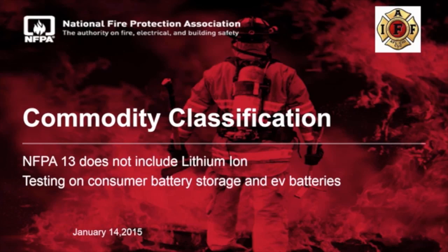But when we put the batteries into an electric vehicle, looking at somewhere around a 300-volt battery, our actual field fire tests showed that if water is used as a suppression agent—the most commonly available and easiest to apply agent for the fire service across America—it has to be there in sufficient quantities, what we call copious amounts of water. For a single battery in our live burn demonstration, the amount needed went from 269 gallons to over 2,600 gallons. That presents a challenge, since the tank on a standard fire engine is probably in the 750 to 1,000 gallon range.